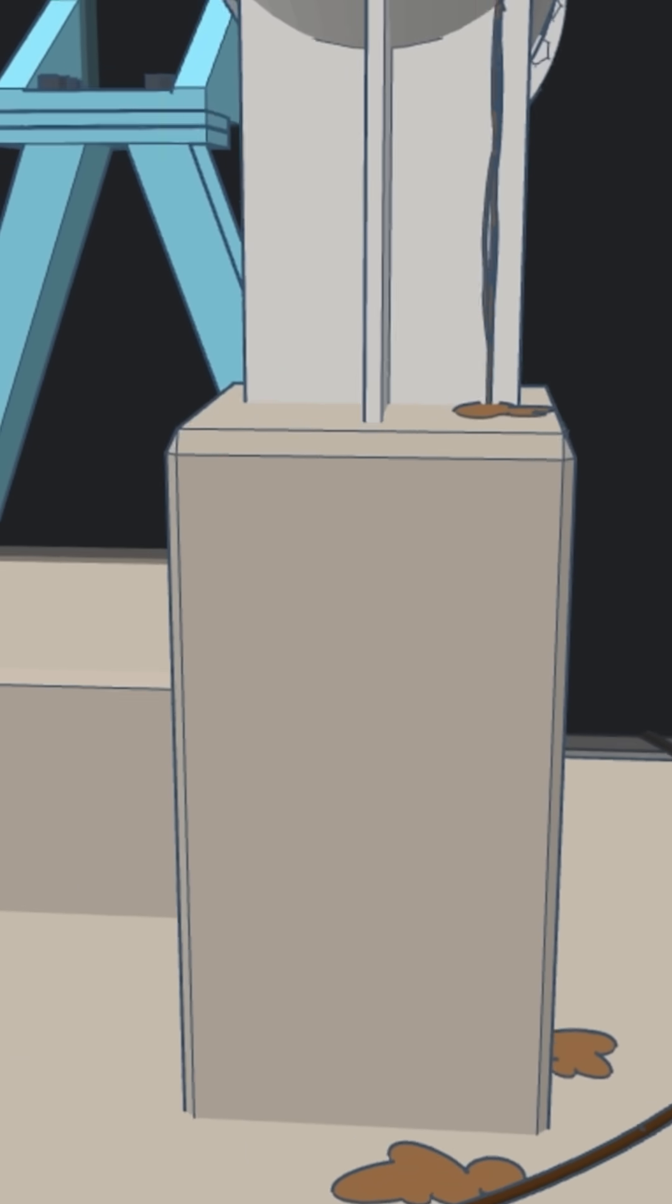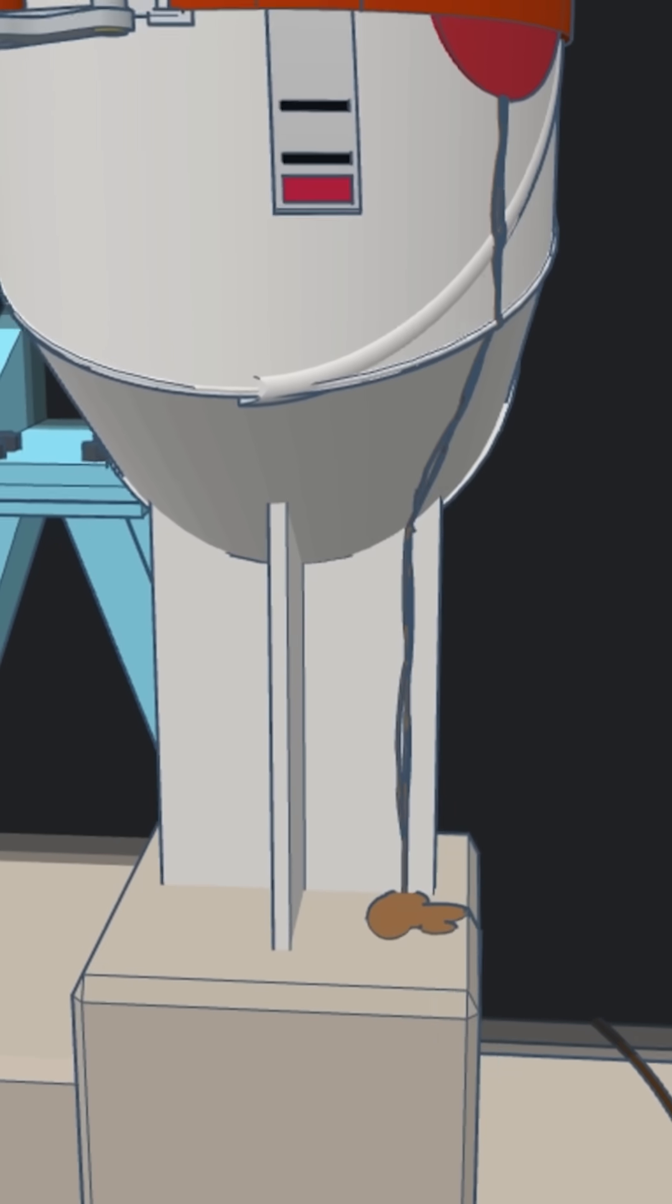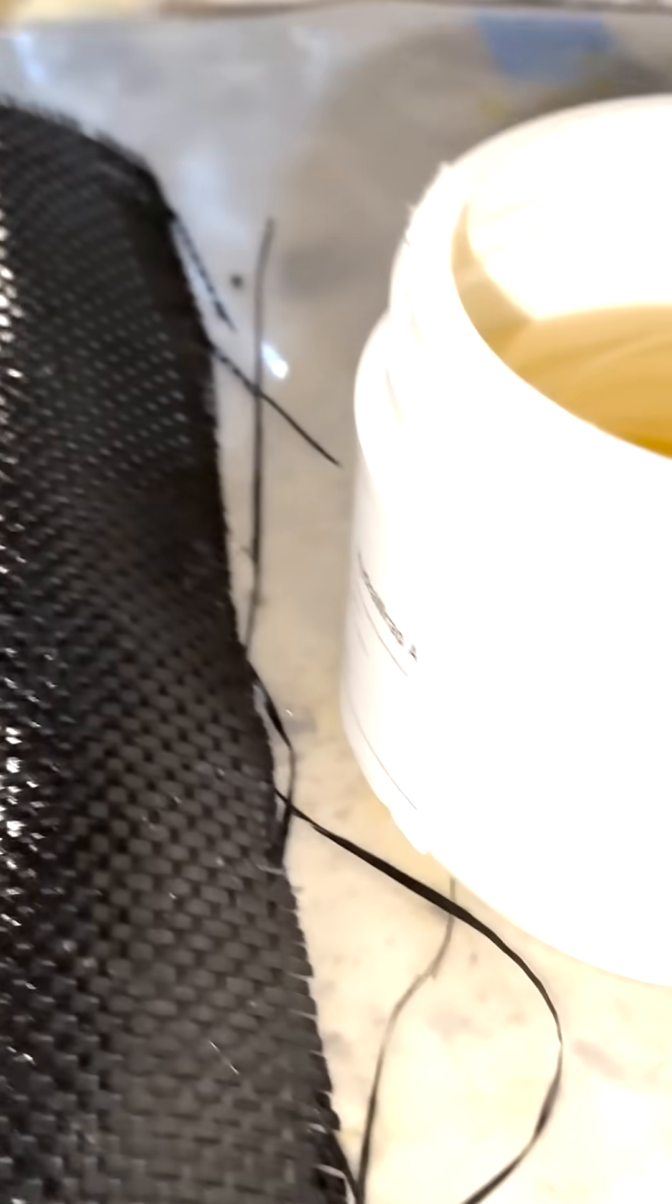A wastewater facility had discovered a problem in one of their reducing elbows. Small holes had formed in the carbon steel. Rather than replace, they chose to rehabilitate this pipe with Hydratex HydroWrap, the composite repair system.